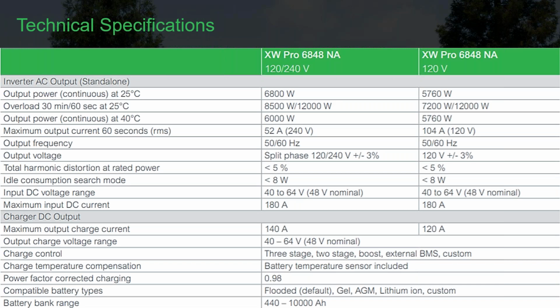Here's the tail of the tape. Be careful when comparing to competitors' technical specifications, as some express peak power, that is 1.4 times higher than RMS power, which does the actual work. Note the specifications for 120 volt, which are relevant for three-phase configurations with XW Pro. The limitation for continuous output is due to the 60 amp breaker size when applying the 80% rule. NEC defines continuous power as 3 hours or more, so it is possible to obtain full power for periods of less than 3 hours.